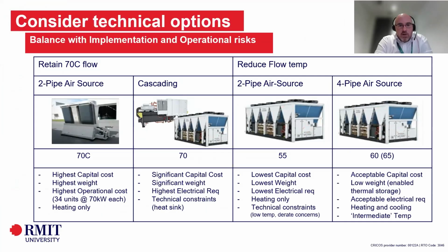So we looked at the technical options, and we tried to balance the implementation and operational risks with the technical outcome. The option was to retain the 70-degree flow temperature, and in order to do that, we could use a two-pipe system with air source or cascading, or we could look to reduce the flow temperature. And that opens up a lot more alternatives and also lower cost alternatives. So ultimately, we ended up going with a four-pipe air sourced unit, and that was due to the ability to simultaneously heat and cool, because we could access a large cooling load for most of the year. And also that was a low weight and an acceptable electrical requirement to deliver that solution.